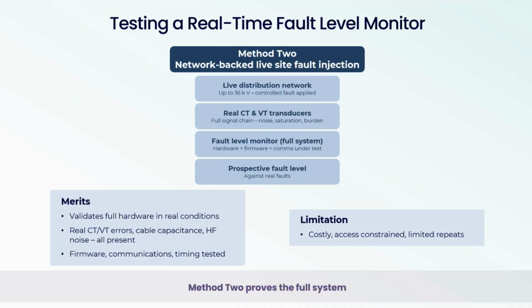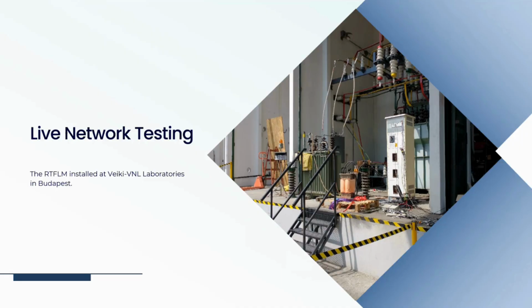We explored a facility in Australia, and we also explored one in Hungary, the Veiki-VNL laboratories in Hungary. And the one in Hungary turned out to be the best option for us. They've actually got a test network there that's fed from the Hungarian grid, so we've got real representative fault level. And as part of their facilities, they could close a breaker to throw a solid earth fault and actually measure the fault current. So just move on to the next slide. I think there might be a photo. There we go.